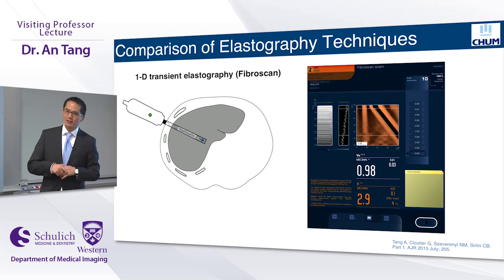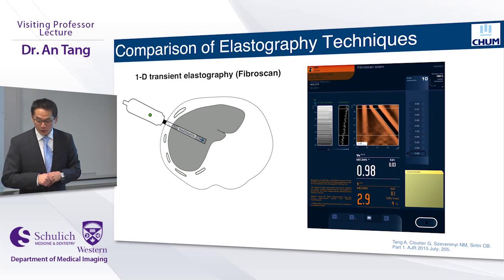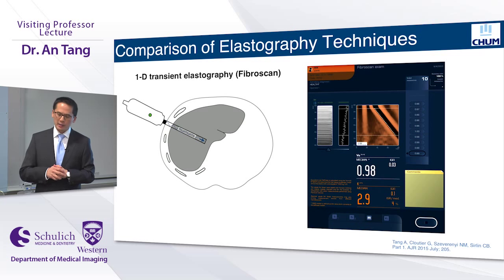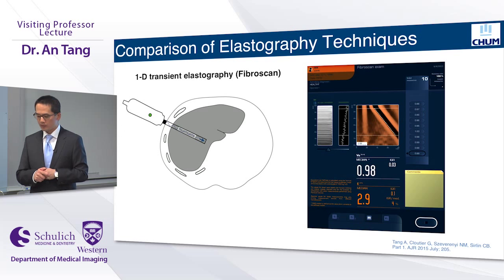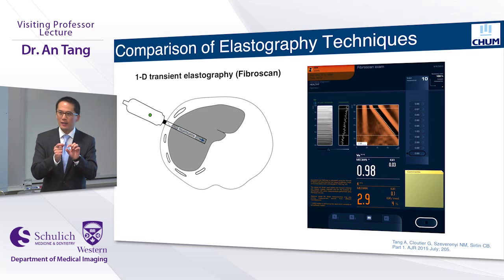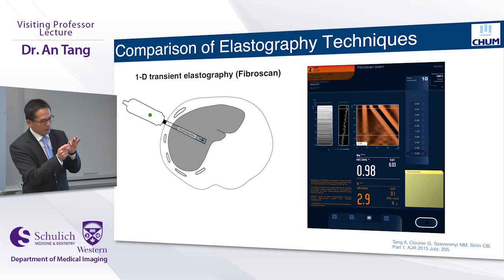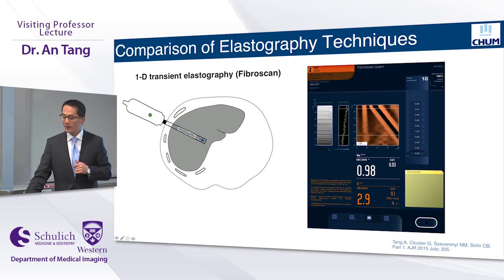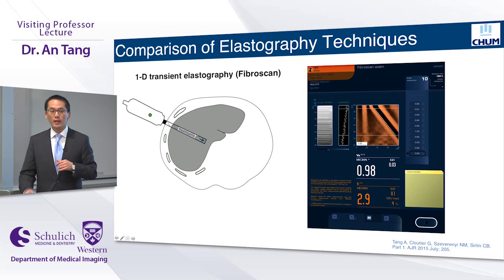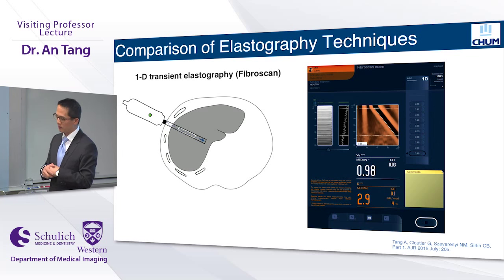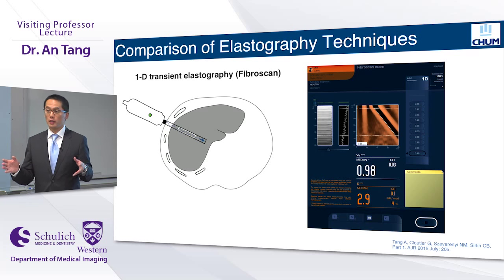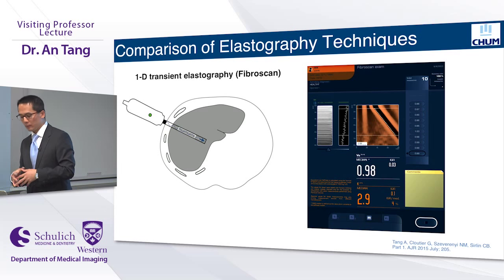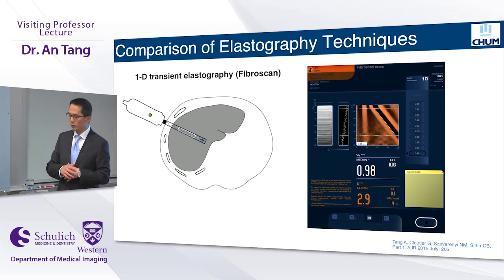You may have heard of 1D transient elastography, commercialized as Fibroscan by Echosens, used as a point-of-care instrument by hepatologists and internists to assess liver fibrosis. This machine is essentially a piezoelectric crystal mounted on a vibrating piston placed against the skin at an intercostal location. Shear waves are propagated in the liver tissue and tracked with ultrasound beams at very high speed. Depending on the shear wave speed, we can assess liver stiffness. This technique doesn't produce an anatomical image — there's no B-mode image, just M-mode and A-mode images — and based on the slope, we can estimate liver stiffness.